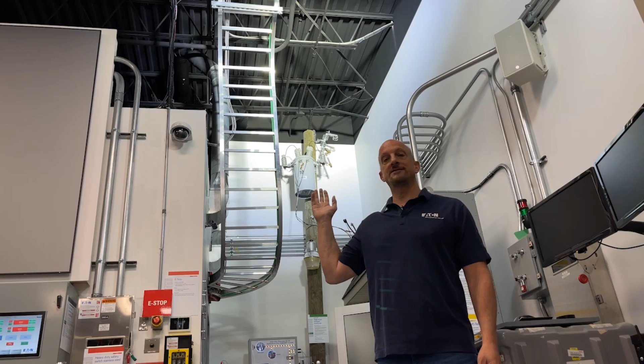Now here's a transformer on a pole. We can see it's single phase. It's 13,800 volts on the input and 240/120 coming into your house in the output. How are you going to figure out what size that one is? Well, we can see the 10 on there. What that means is 10 kVA. But the problem is, unless I climb that pole, I don't know what the transformer impedance is. So we're going to have to make some assumptions on this one.